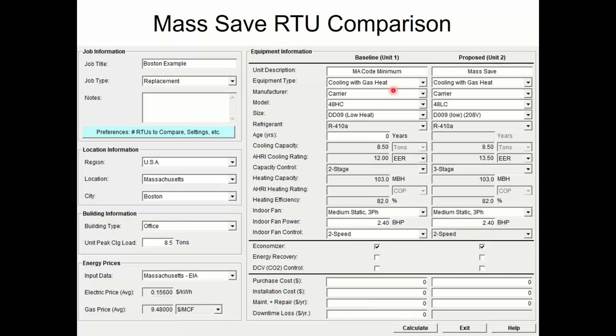The only temperatures that are involved in this discussion are going to be the economizer. Well, the only temperatures you can adjust are picking the weather data. You cannot actually on this tool go in and adjust any other temperatures. You can't adjust the economizer temperature. You can't adjust the weather temperature. You cannot adjust the indoor temperatures. On the full HAP modeling tool, you can adjust all of those things if you want to. But on this tool, it's assuming that on both options, the outdoor air would be the same. It's assuming that on both options, your thermostat set point would be the same. So it's removed all of the options like that so you can do things really fast.